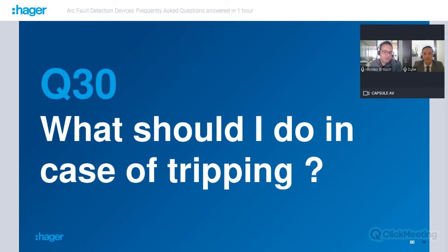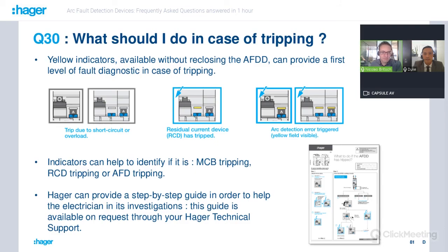Okay, Duke, a question that also came a lot of times. What should I do in case of tripping of an AFDD? So we're talking about the identification of the kind of fault when the AFDD trips, right? We have different indicators. Yellow indicators help to identify if it is the MCB tripping, the RCD tripping, or the AFDD tripping. So when there is a fault in the network, you will know which kind of cause or fault happened. And we have a step-by-step guide and all the related support to help you during the life of the AFDD. It's very clear and very smart. The product can identify and give you a lot of information, necessary for your operation.